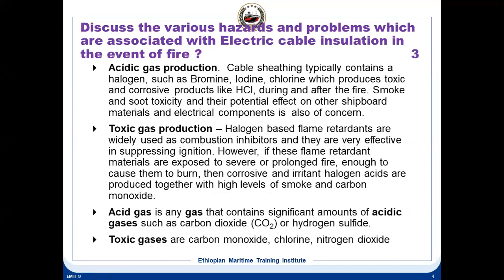The other part, in the same question, says to suggest remedies for these problems. Cable having EPR, ethylene propylene rubber insulation, with necessary sheathing of polychloroprene, PCP, or chlorosulfonated polyethylene, CSP, may be used to protect insulation against fire. Also, a galvanized armor may be used to protect insulation from fire.